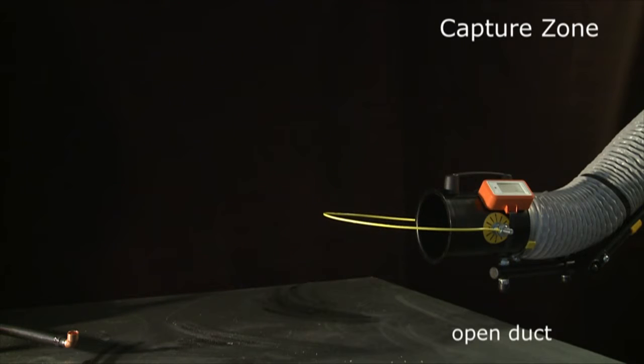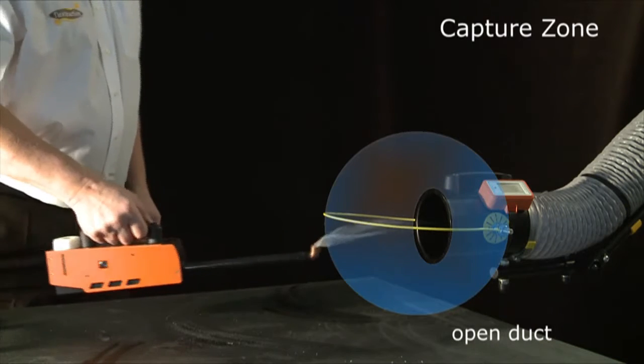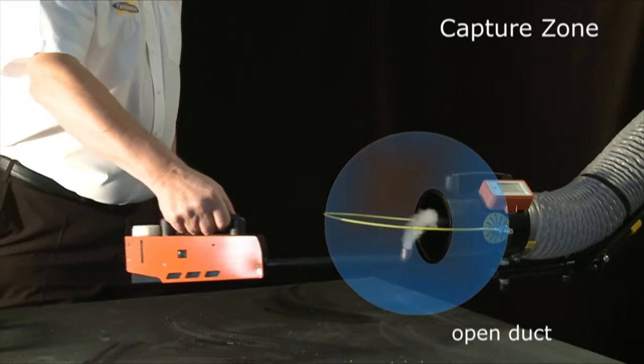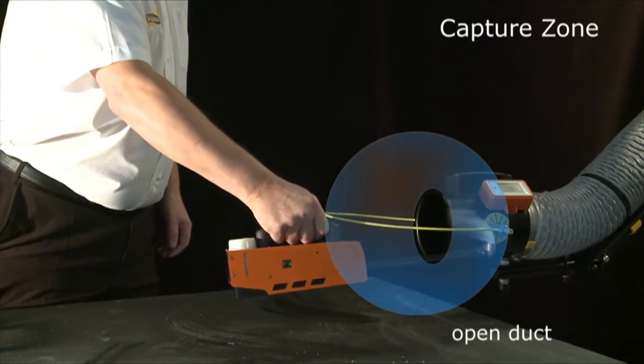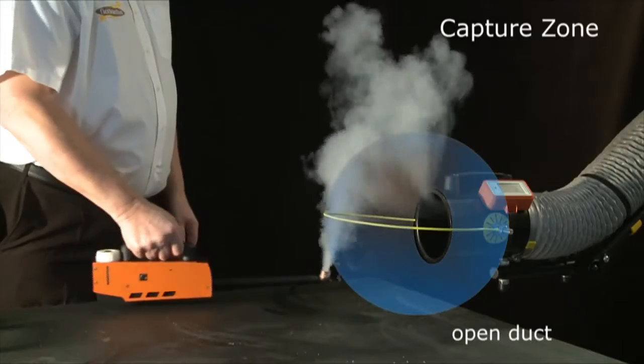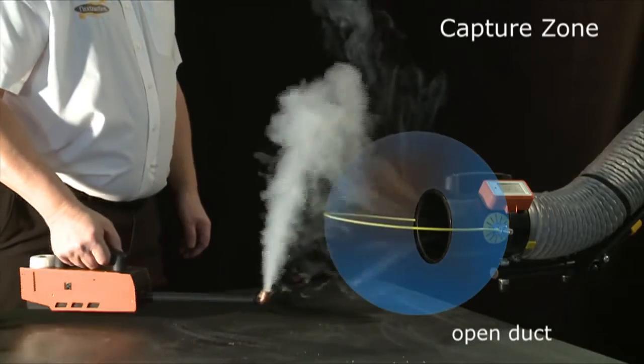The capture zone is the space in front of the hood where the air velocity is sufficient to capture the contaminant cloud. One way to envisage it is as a bubble in front of the hood. Inside the capture zone, almost all the contaminant will be captured. Outside the zone, almost all the contaminant will escape.